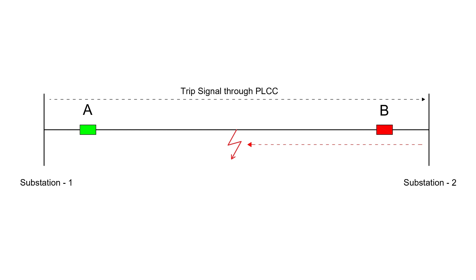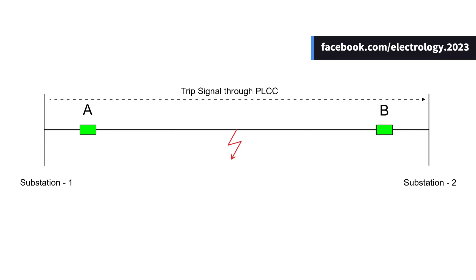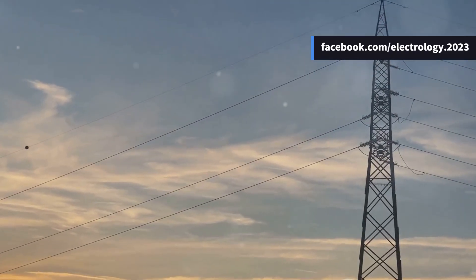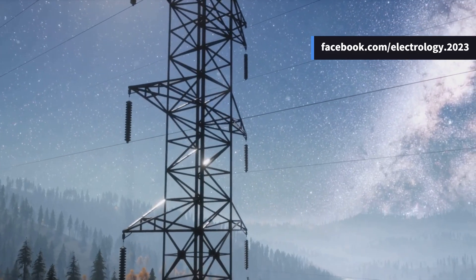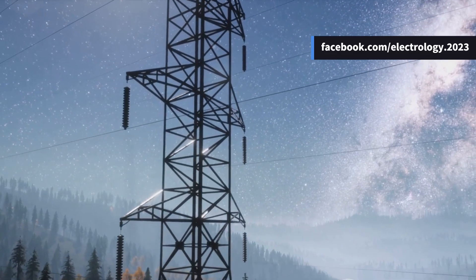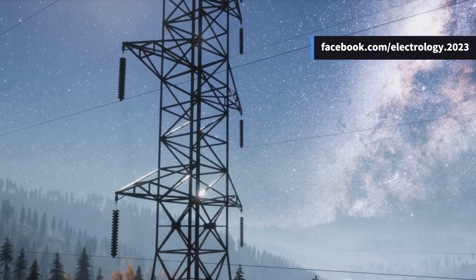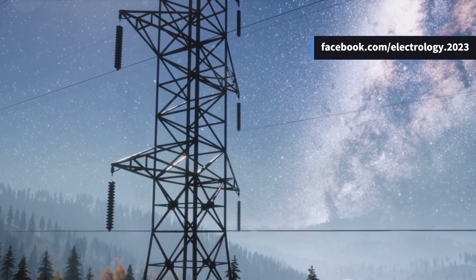This trip signal is crucial to ensure that the breaker at Station 2 also opens, isolating the fault entirely. Aside from the direct trip signal, PLCC also transmits signals for auto-reclosure to ensure quick restoration of the system. Now, let's break down the main components of a Power Line Carrier Communication system. Each part plays a vital role in the operation and protection of the power system.